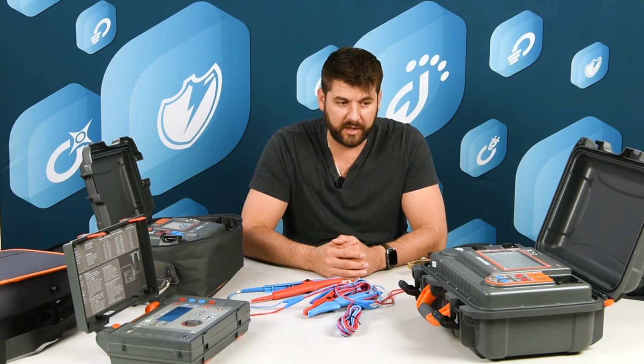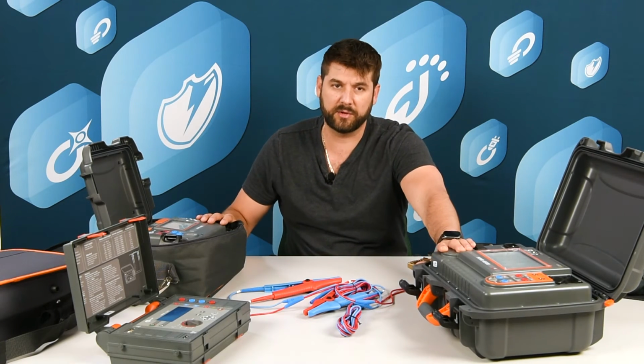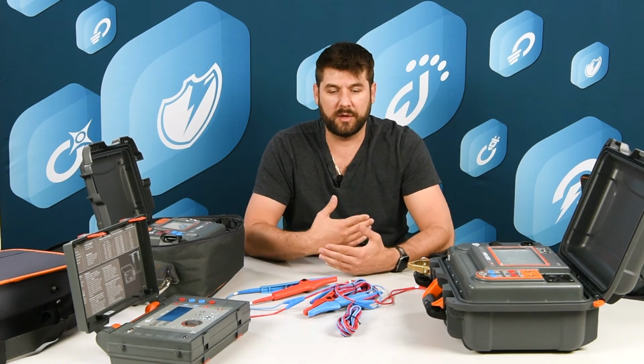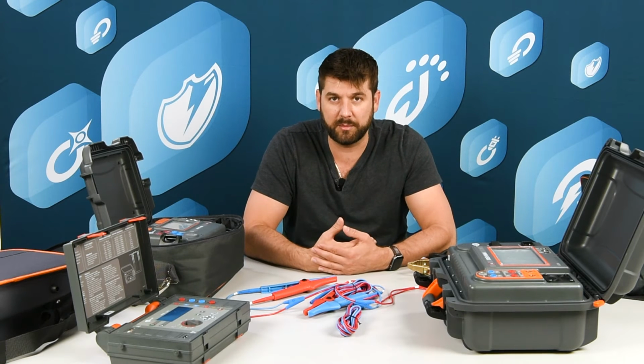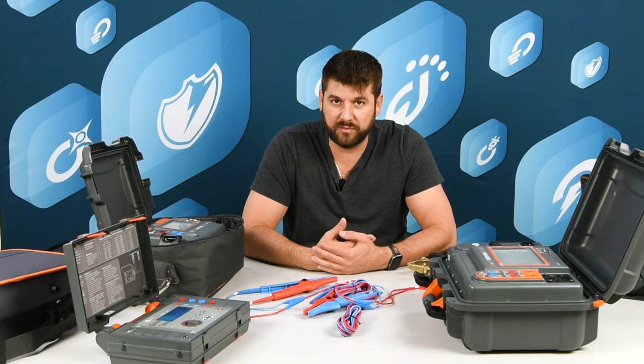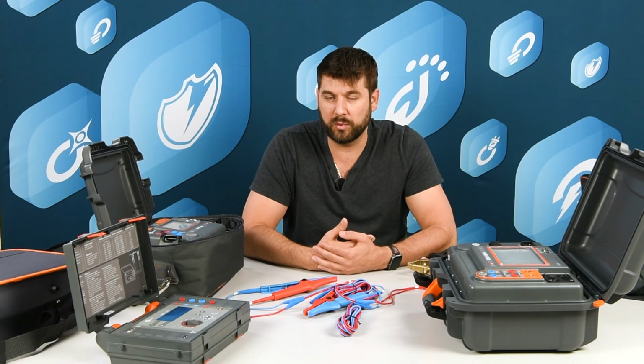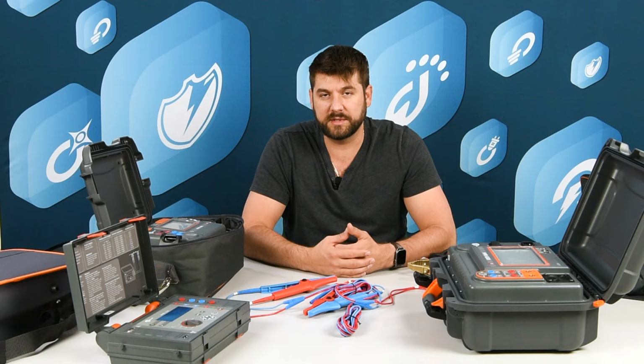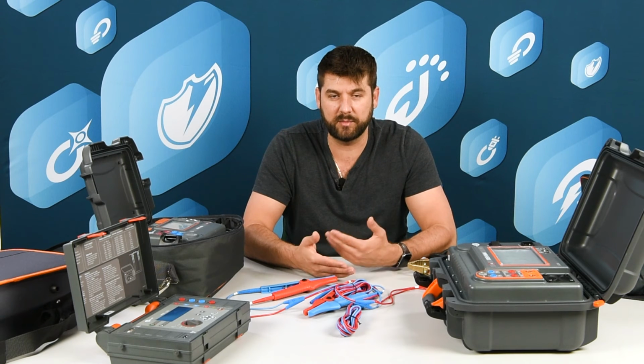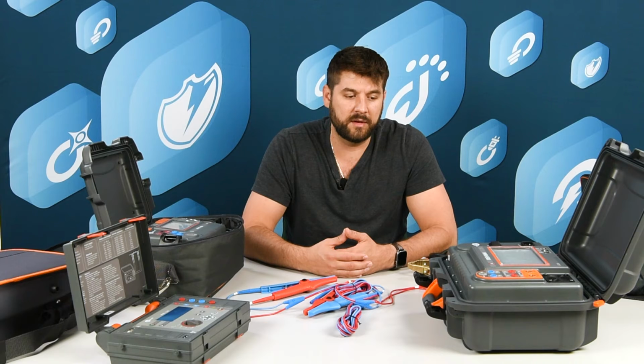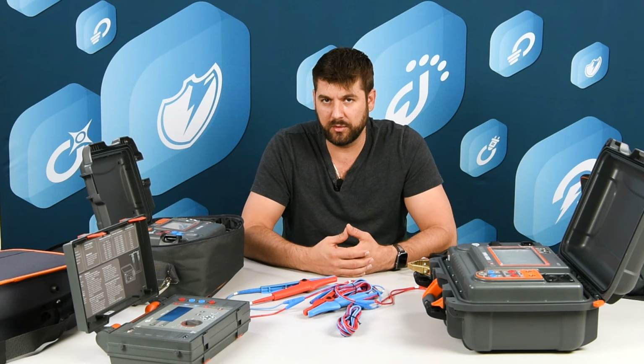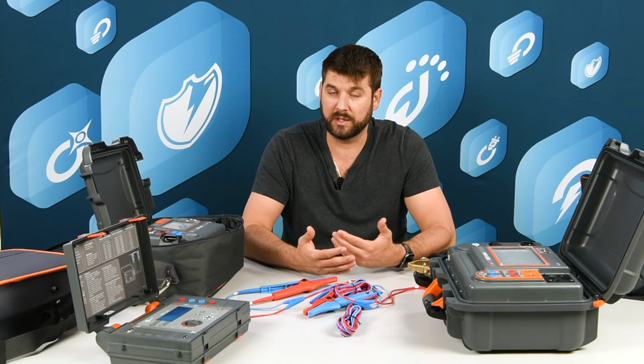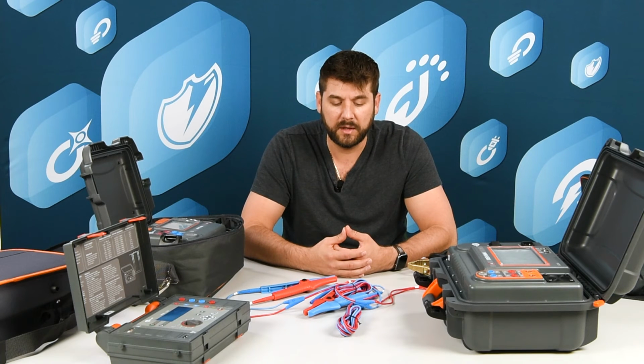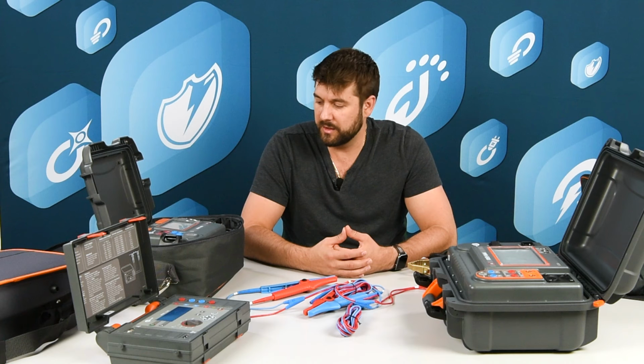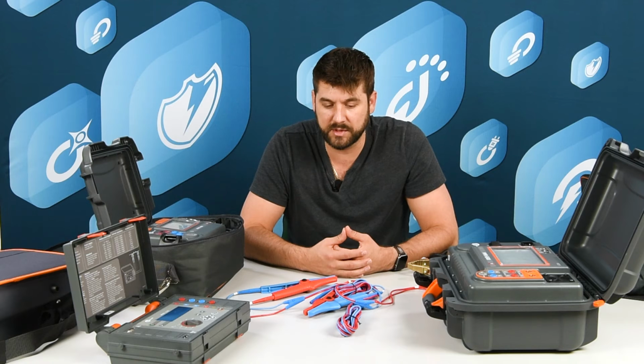Now, these instruments I'll mention right now, also the 650 and the 6500, 6700, they're also equipped with temperature probes to measure the temperature for temperature compensation. They have a demagnetization function, so if you're measuring a coil or a winding, something with a core, you build up a DC field inside, and this is going to be able to discharge that and demagnetize the core. And these instruments also have circuitry to handle an inductive object like a winding or a coil.